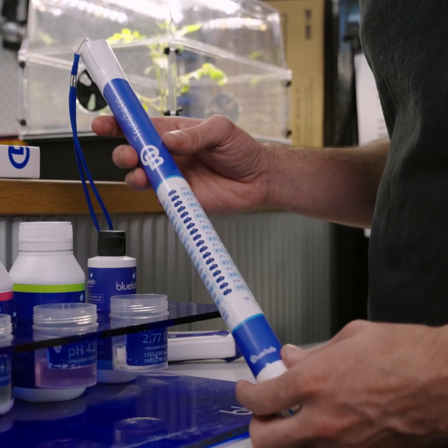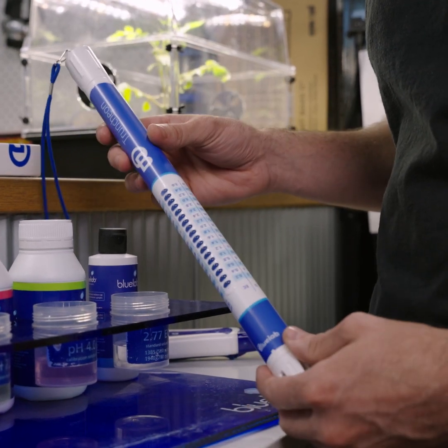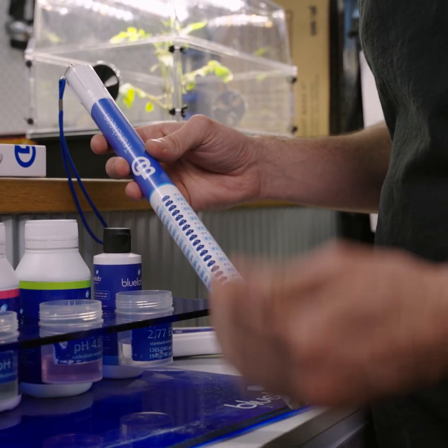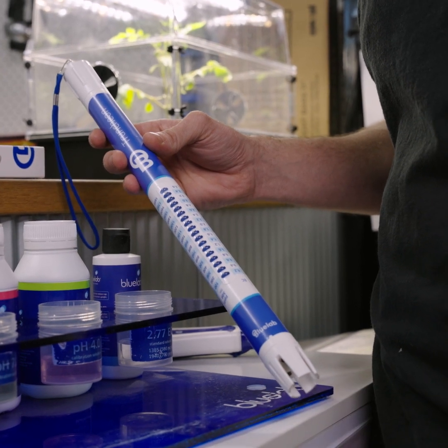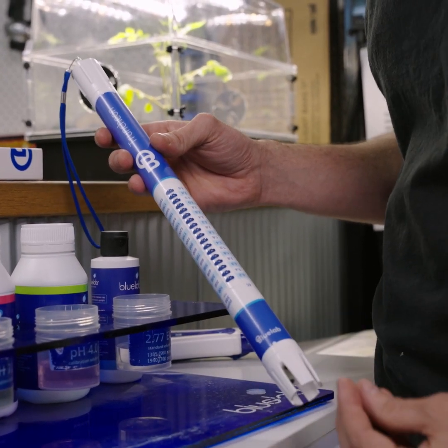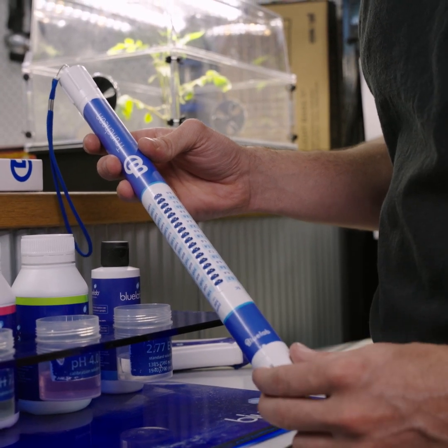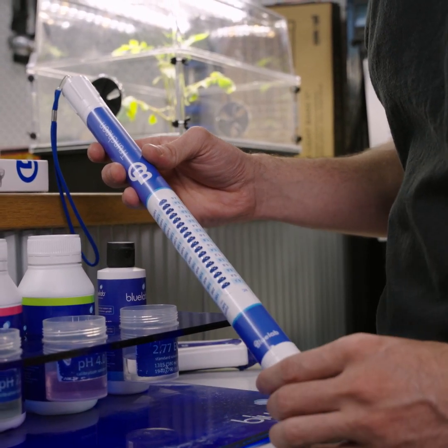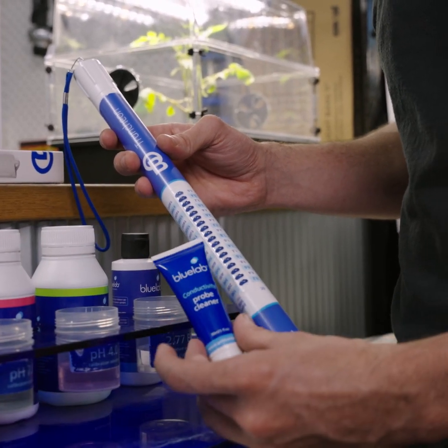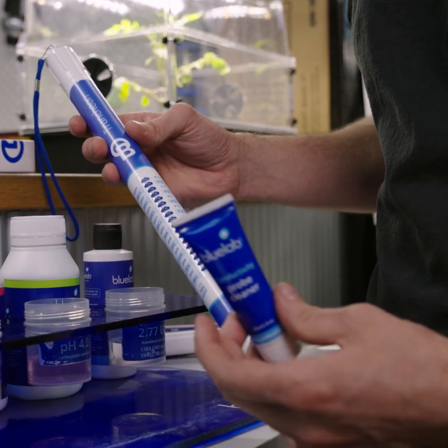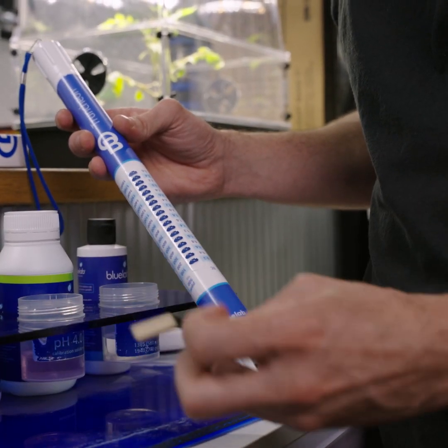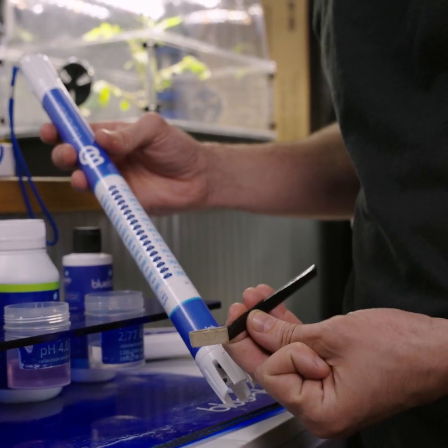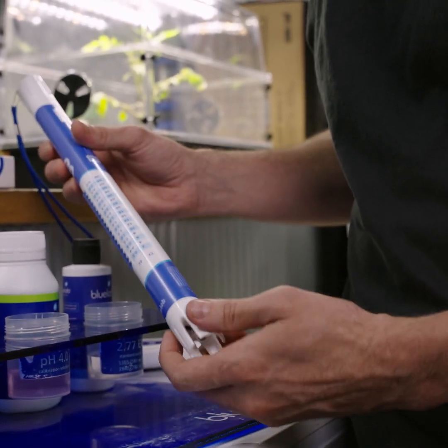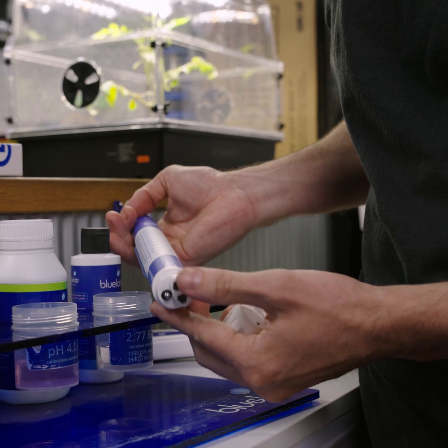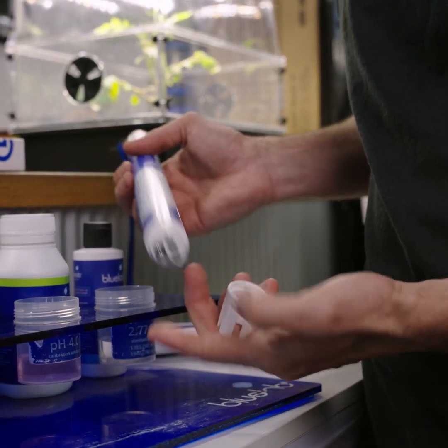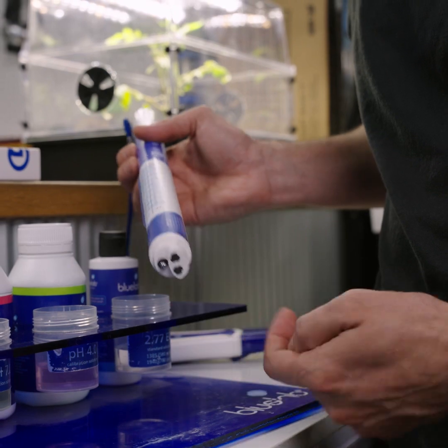So with the EC pens, or we're using the truncheon here just to show you how simple it is, it doesn't necessarily need to be calibrated. Some do, some brands require you to. This is more just checking that it's reading correctly. Because these are a much simpler probe, they're not as temperamental. In the care kits, you still get a probe cleaner, so you can clean the top of this, and you get the little sort of fine brush to scrub across the top. So this actually screws off here, which is how you clean that probe there. And you can use it with or without this. This is just to stop you from bashing the top.